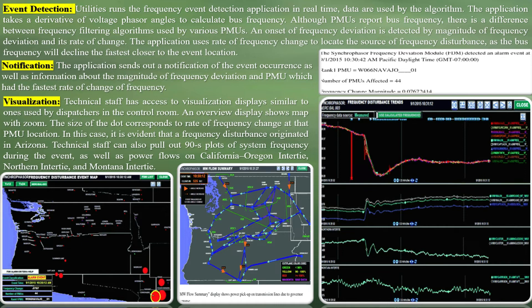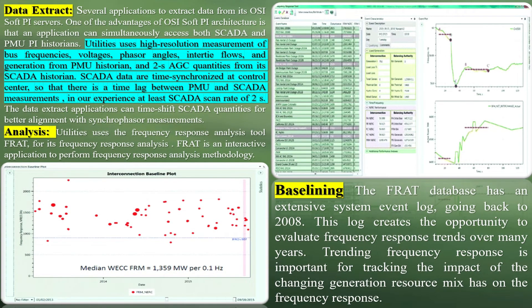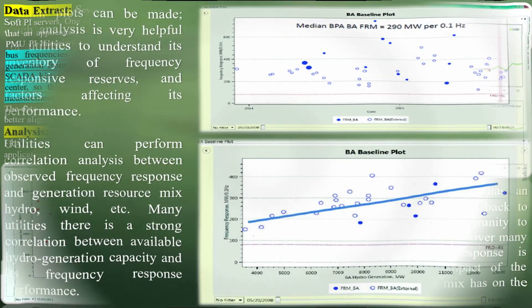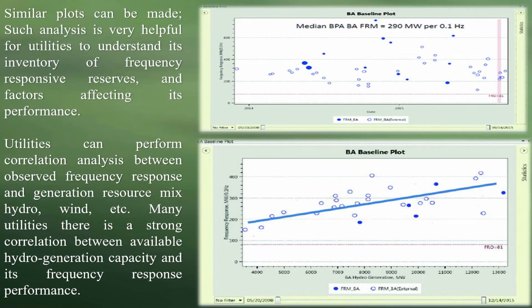Notification: the application sends out a notification of the event occurrence as well as information about the magnitude of frequency deviation and the PMU which had the fastest rate of change of frequency. Visualization: technical staff has access to visualization displays similar to those used by dispatchers in the control room. An overview display shows a map with zoom. The size of the dot corresponds to the rate of frequency change at that PMU location. In this case, it is evident that a frequency disturbance originated in Arizona. Technical staff can also pull up 90-second plots of system frequency during the event, as well as power flows on the California-Oregon Intertie, Northern Intertie, and Montana Intertie.